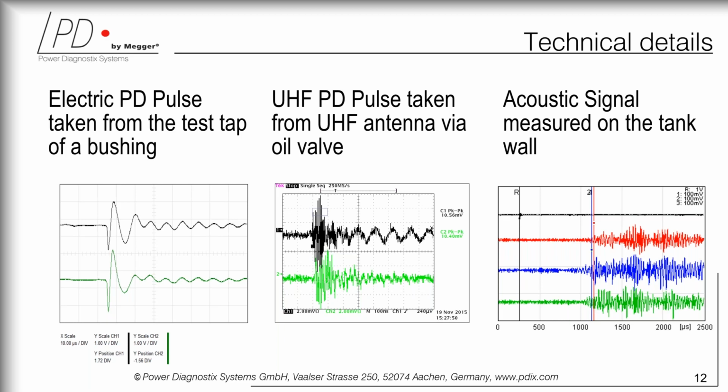What is very interesting is to actually have all these sensors and monitor all these channels, because the bushings are important, what's happening within the tank is important, and of course acoustically we can even locate which areas are problematic if we decide to actually do service on that particular transformer.